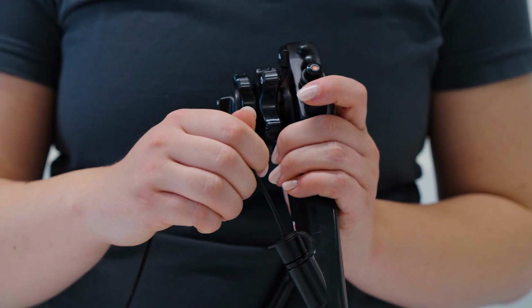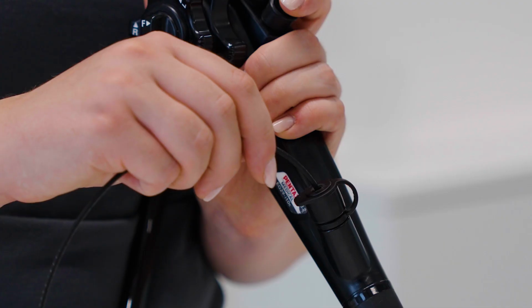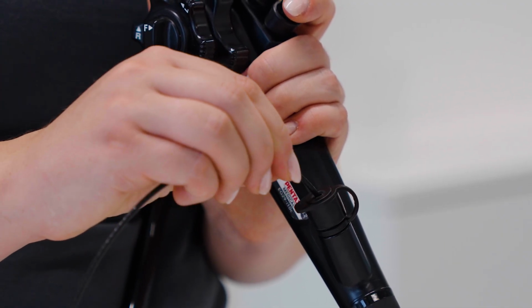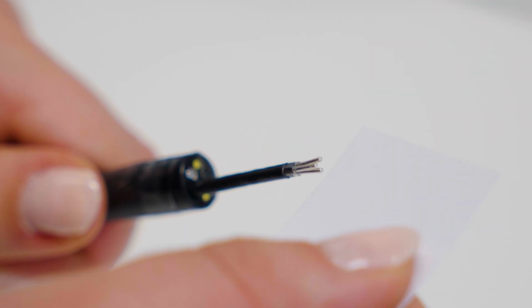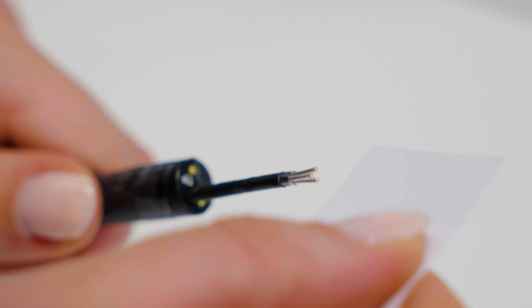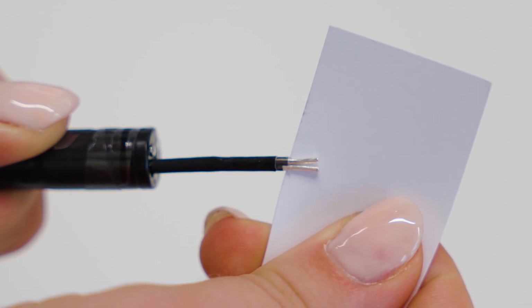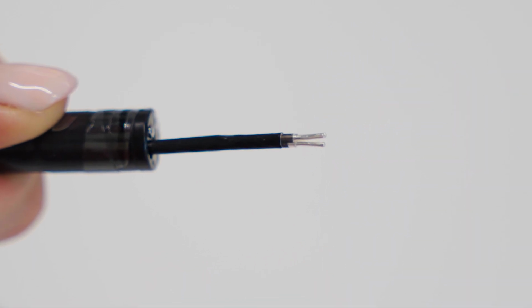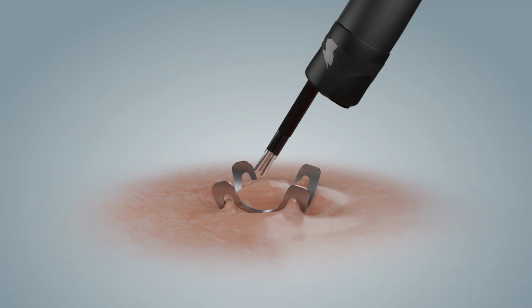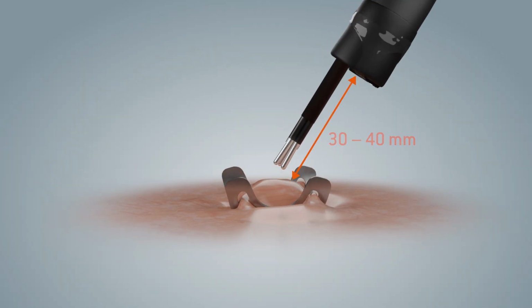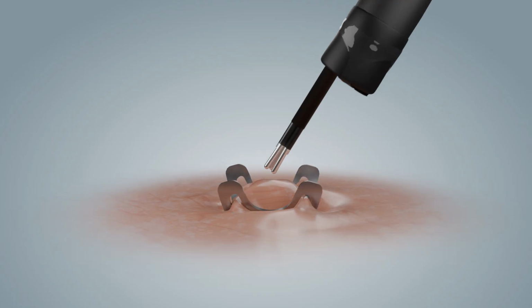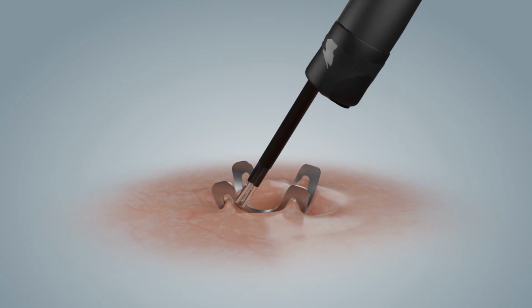Introduce the remOVE DC cutter through the working channel. If you hear a continuous tone upon insertion, remove the instrument from the patient and carefully separate the 3 electrodes of the cutter tip, for example with a piece of paper. For an optimal view during the cut, maintain a distance of 30 to 40 mm between the endoscope tip and the clip. Now establish contact with the clip.